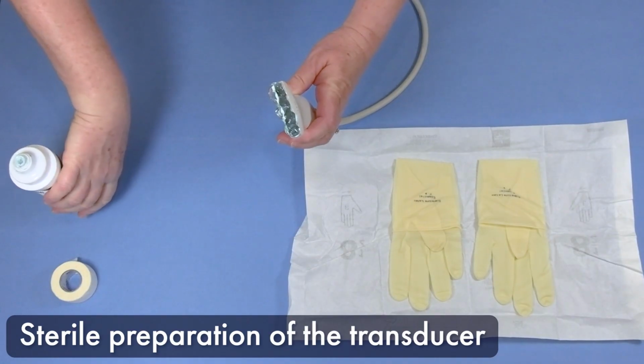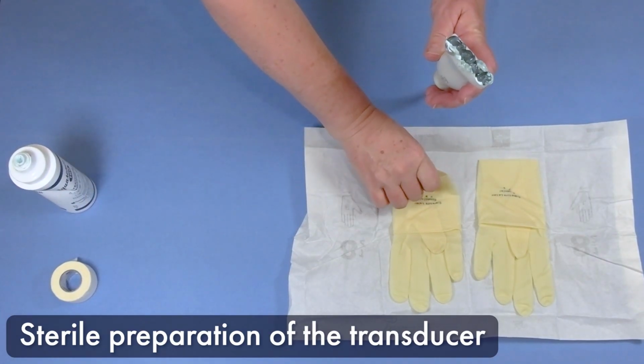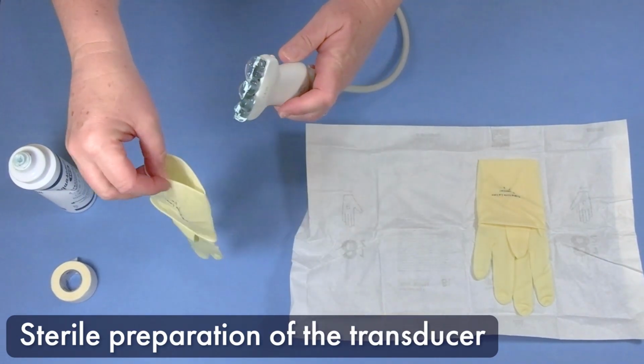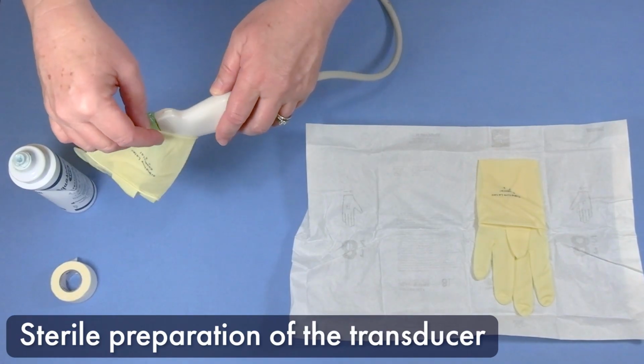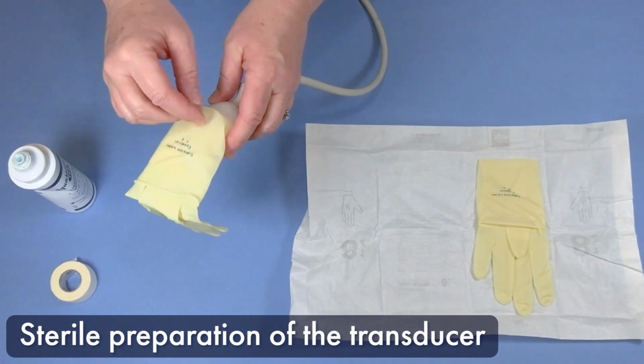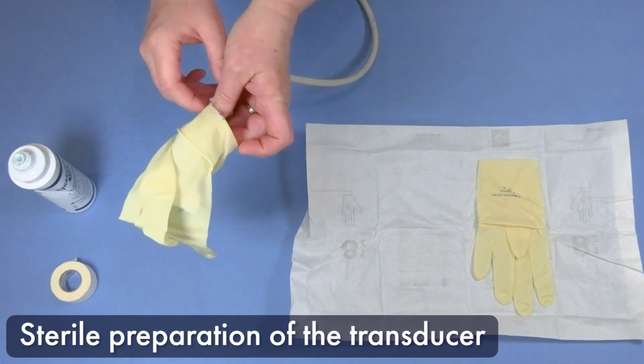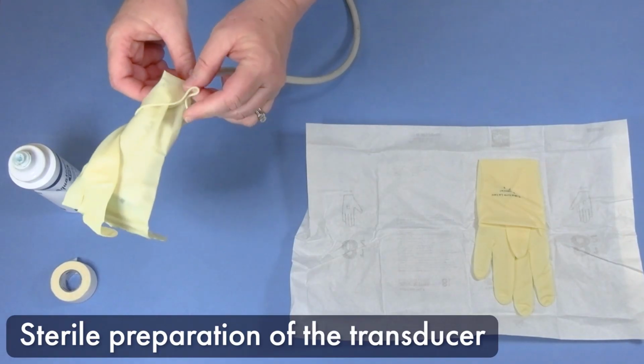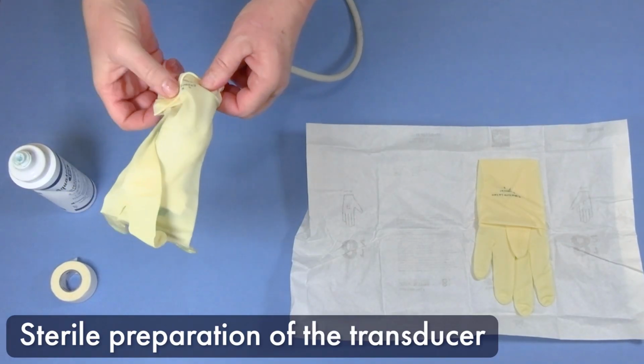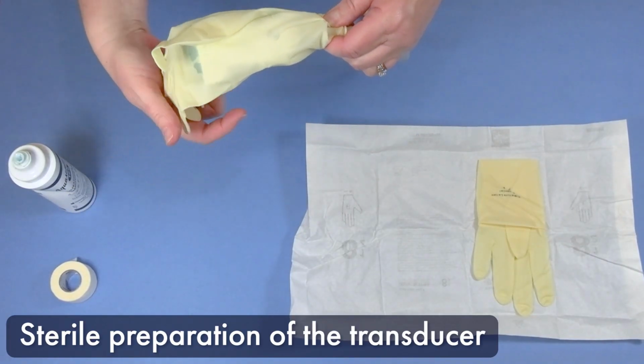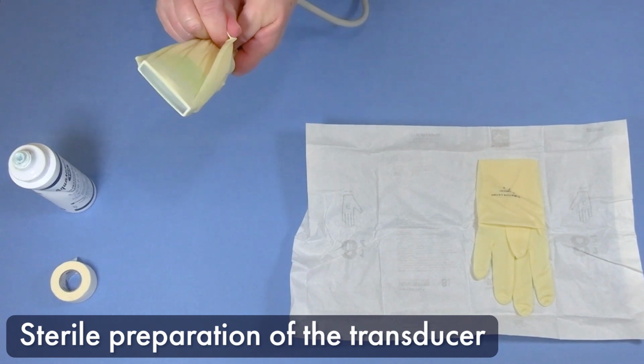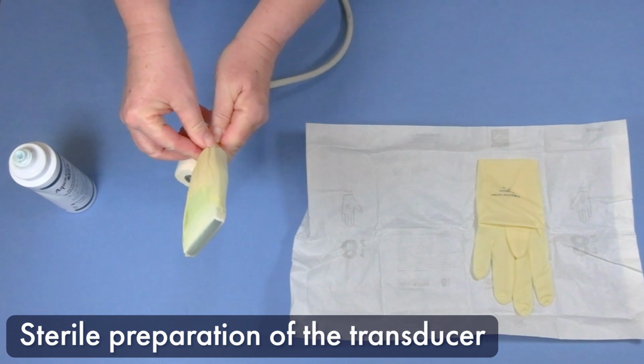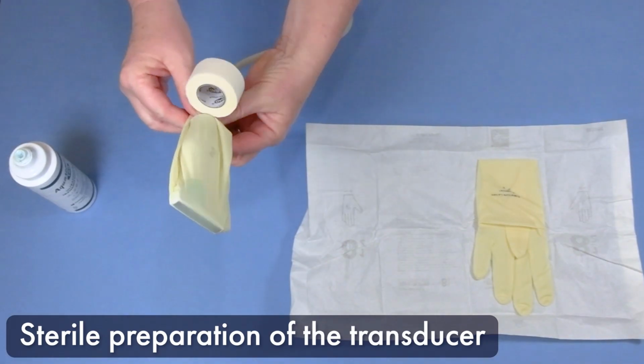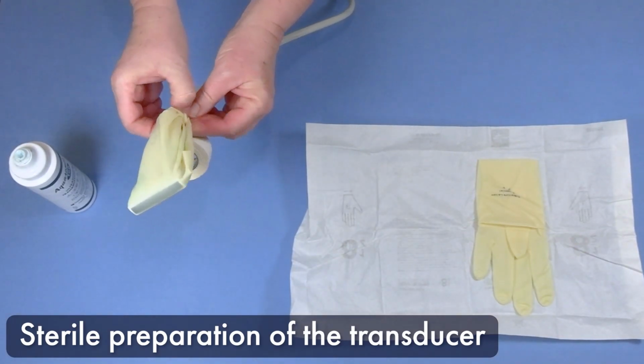Apply ultrasound gel to the probe. For extra precaution, sterile gel can be used. Pick up the sterile glove and open the cuff as wide as possible to insert the probe. Slide the probe smoothly into the glove, ensuring the glove fully covers the length of the probe. Pull the glove down to extend it completely over the base of the probe. With your other hand, fold the glove's fingers and thumb back towards the probe. Secure the glove at the base of the probe with tape to prevent slippage and maintain sterility.